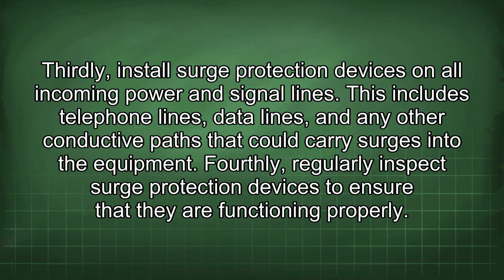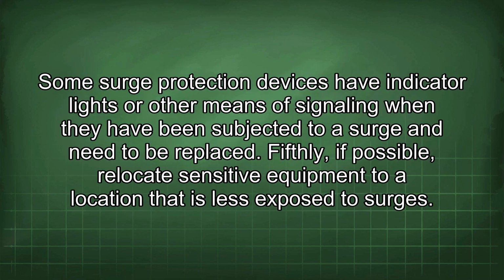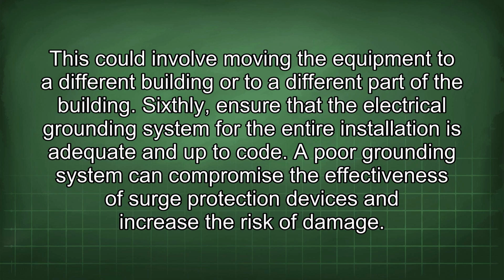Fourthly, regularly inspect surge protection devices to ensure that they are functioning properly. Some surge protection devices have indicator lights or other means of signaling when they have been subjected to a surge and need to be replaced. Fifthly, if possible, relocate sensitive equipment to a location that is less exposed to surges. This could involve moving the equipment to a different building or to a different part of the building. Sixthly, ensure that the electrical grounding system for the entire installation is adequate and up to code. A poor grounding system can compromise the effectiveness of surge protection devices and increase the risk of damage.